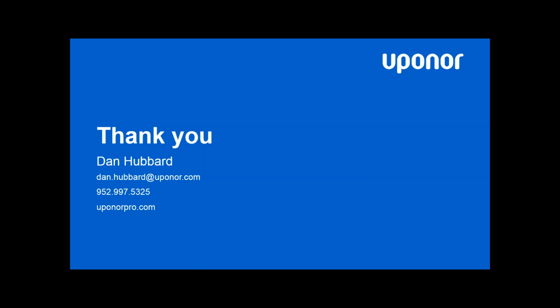One thing that's beautiful about Uponor's design team is because they've done so many of these systems, they know, okay, if I've got 45, 3/4 will work. If I've got 1-inch, I need 20 to 35 PSI, and I can make that system work. So it takes about a 5-minute conversation with the design team to figure out if your underground is big enough to make those pressures work.